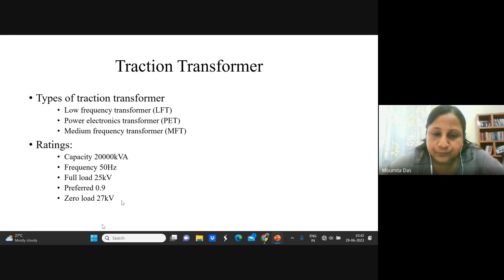Now, what is the difference between this power electronics transformer and the line frequency transformer? As I said, the line frequency transformer should be able to take 15 kilovolt 16.7 hertz or 25 kilovolt 50 hertz, which are generally used for railway catenary systems. And the power electronics transformer basically operates at medium frequency. Earlier the concept was medium frequency, basically from hundreds of hertz to tens of kilohertz, and that is known as a medium frequency transformer.